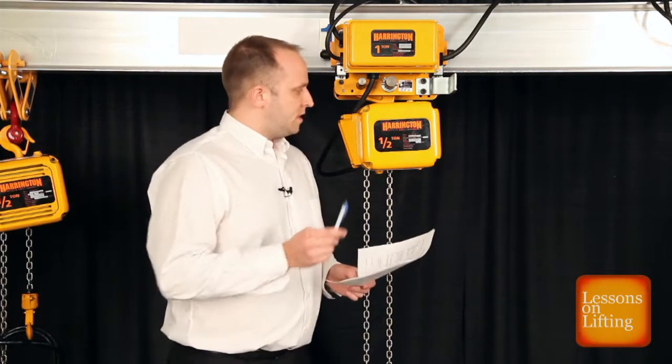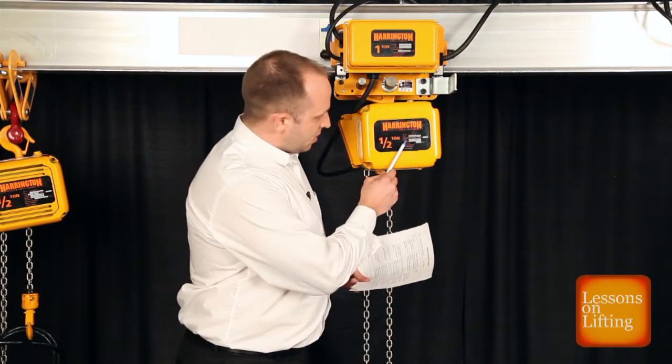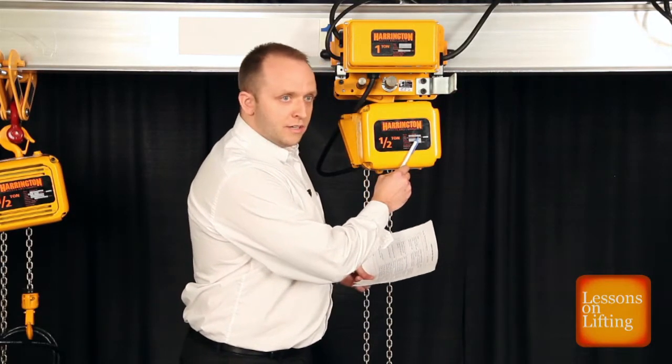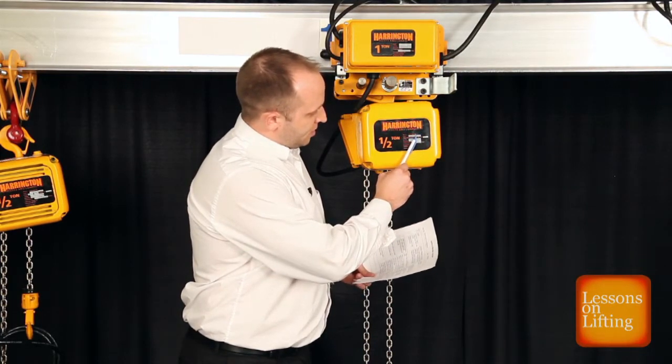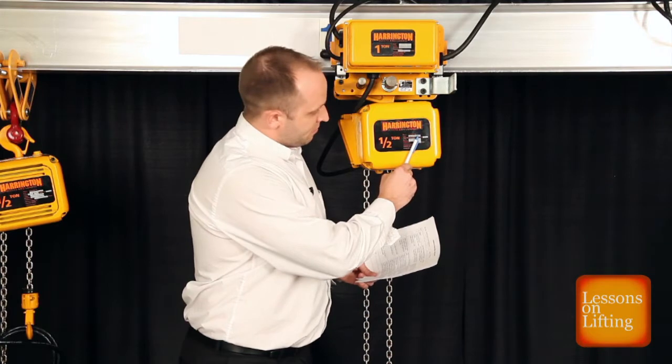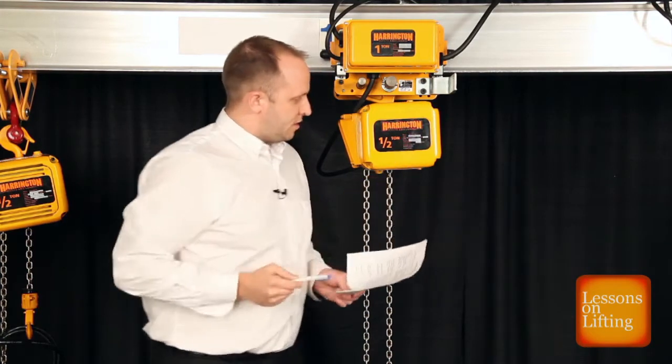One way you can tell if it's single or dual-speed is to take a look at the product code on the hoist cover. Right after the numerical description, there's a letter designator. If it's a single letter, that tells you that you have a single-speed unit and a voltage change is possible.